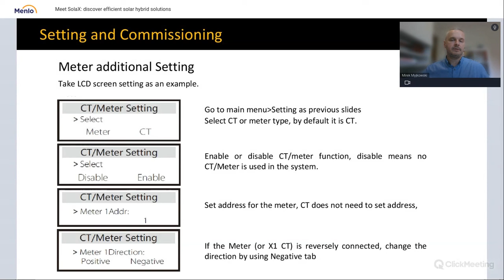We also have positive and negative settings. That means if by mistake an installer connects the meter backwards, it will show as sending to the grid instead of taking from the grid. So that means it's just connected backwards, and you can easily, sitting at home, change this from positive to negative, and all the readings will be interpreted correctly. The inverter will start to read them properly, because it will know it has to negate all the readings the meter sends.